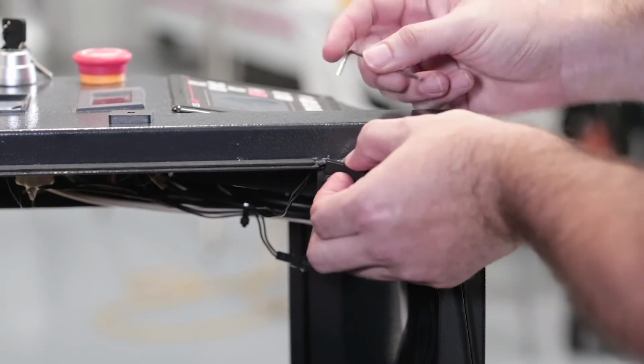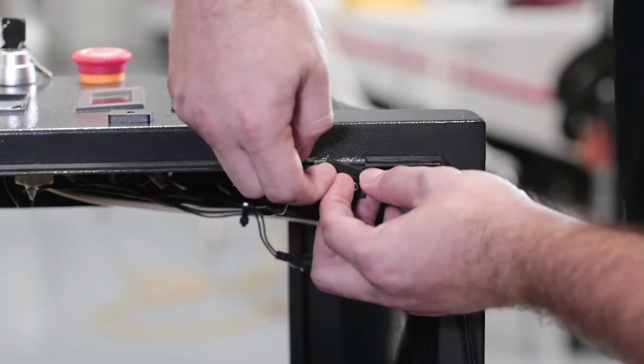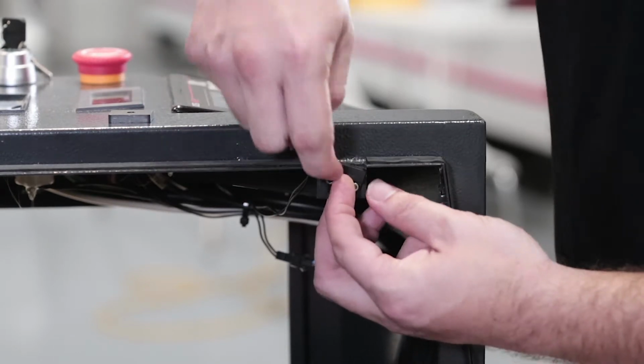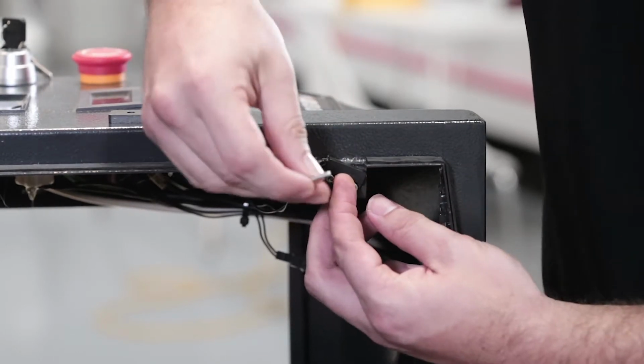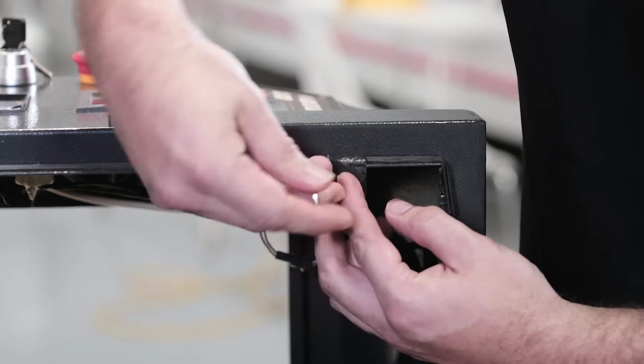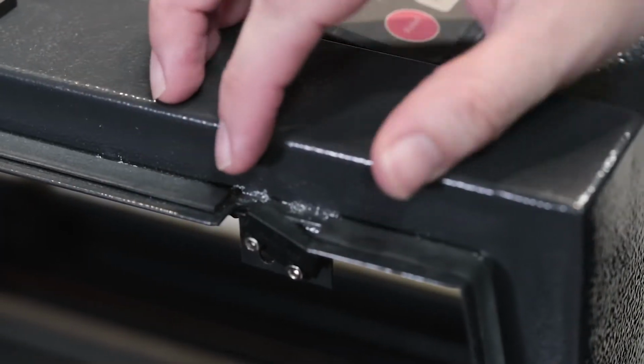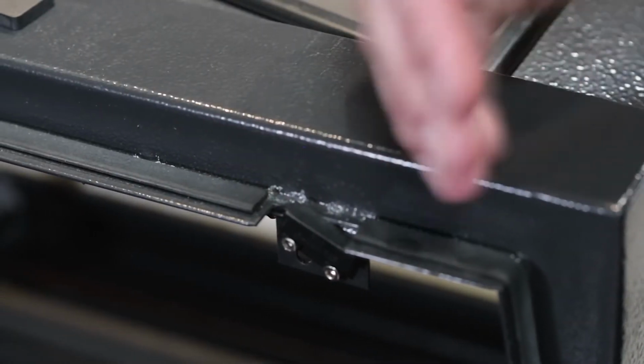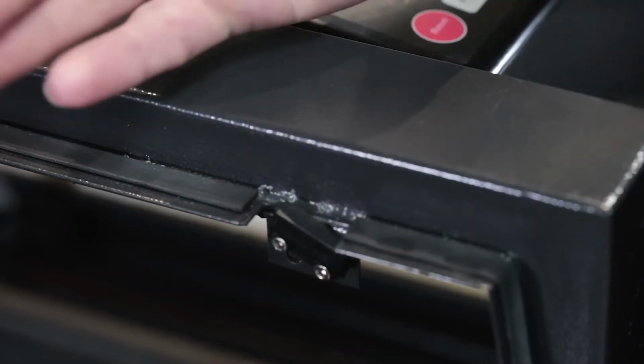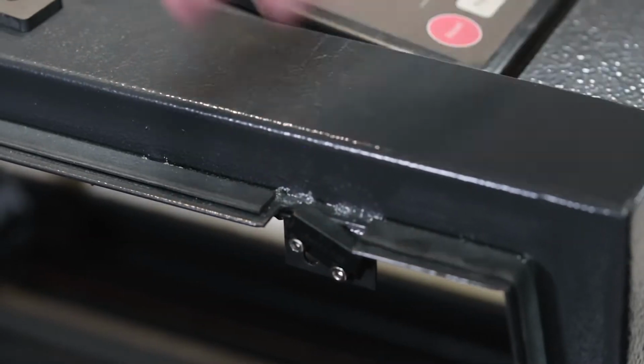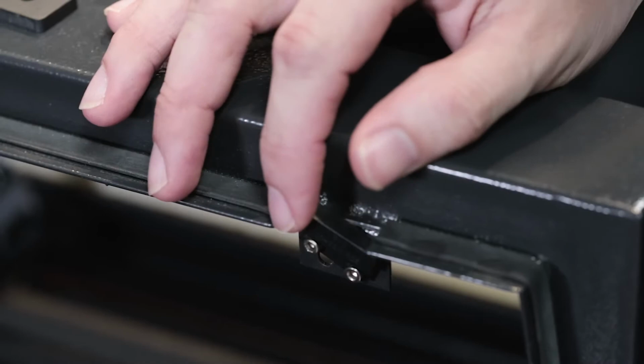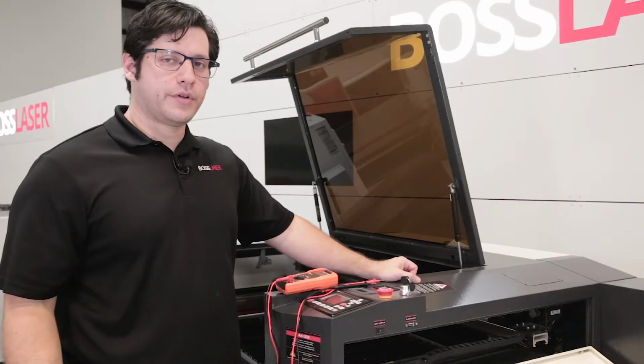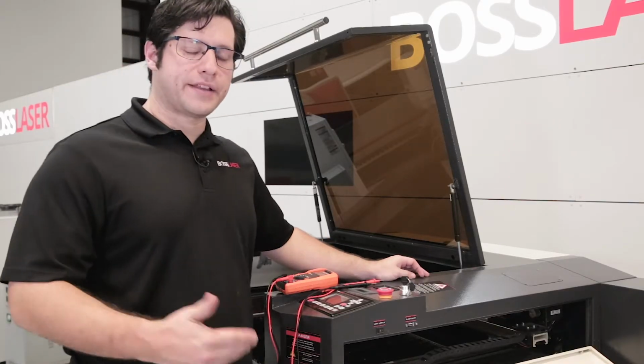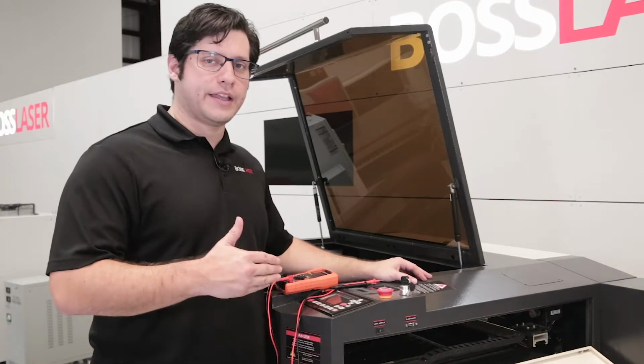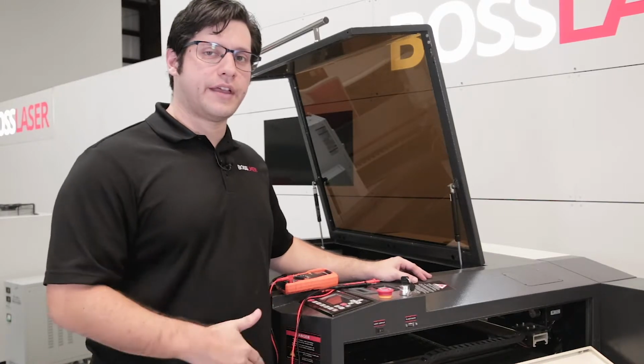You're going to have it adjusted at an angle where it's almost peeking out. So after making the adjustment, go ahead and close your lid and pulse it. If it does fire and you see milliamps moving, that means the issue was that this needed to be adjusted. If your door interlock still is not firing with the magnet placed on top of it, we're going to go ahead and check continuity on that door interlock.